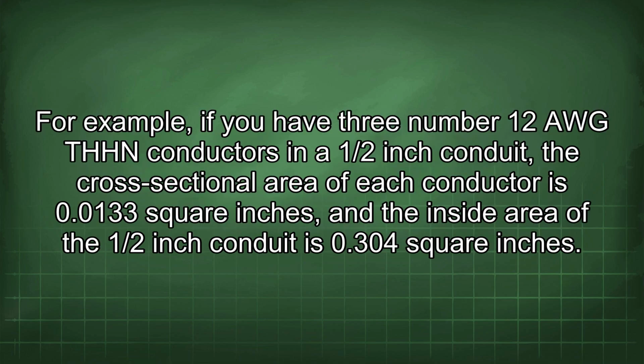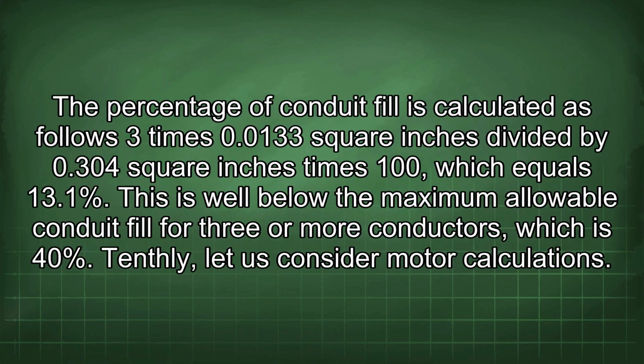For example, if you have 3 number 12 AWG THHN conductors in a 1/2 inch conduit, the cross-sectional area of each conductor is 0.0133 square inches, and the inside area of the 1/2 inch conduit is 0.304 square inches. The percentage of conduit fill is calculated as follows: 3 times 0.0133 square inches divided by 0.304 square inches times 100, which equals 13.1%. This is well below the maximum allowable conduit fill for 3 or more conductors, which is 40%. Tenthly, let us consider motor calculations.